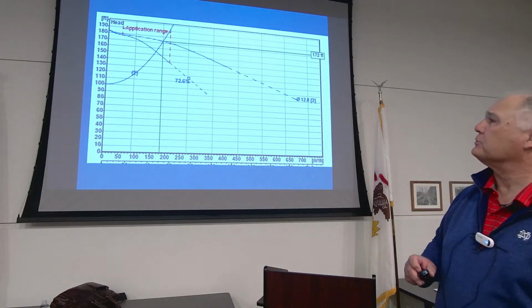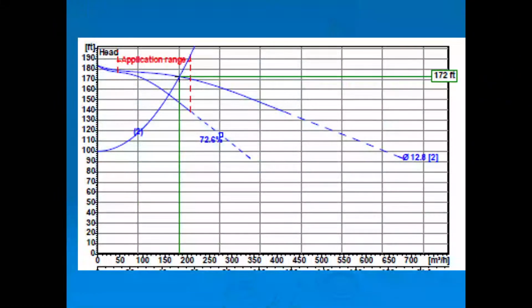So this is a condition of pump 1 and pump 2. This is a 2-pump station, 2 pumps going into the same force main. Same conditions happen. The system curve doesn't matter if it's got 1 pump, 2 pump, 3 pump, 4 pump. It doesn't matter how many pumps it is. System curves are all based on what's in the ground. So therefore, we're starting at 100 feet and we're going up to the right.